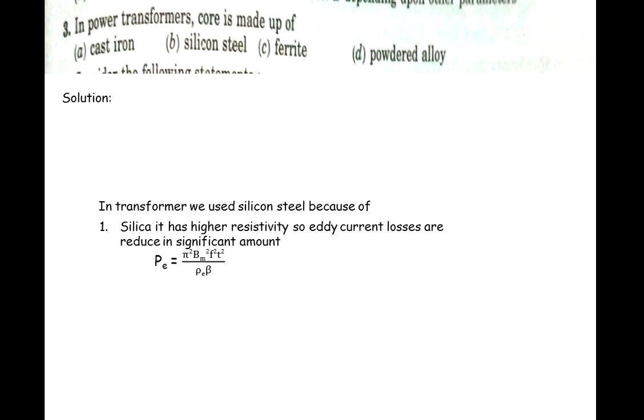Silicon steel has higher resistivity due to the addition of silicon, so eddy current losses are significantly reduced — eddy current losses are inversely proportional to resistivity. This is the first reason. The second reason is that with silicon added, the permeability μ increases, meaning the ability to permit magnetic lines through the core increases. Due to this, overall magnetic capability improves and hysteresis losses are also reduced. So Option B, silicon steel, is correct.